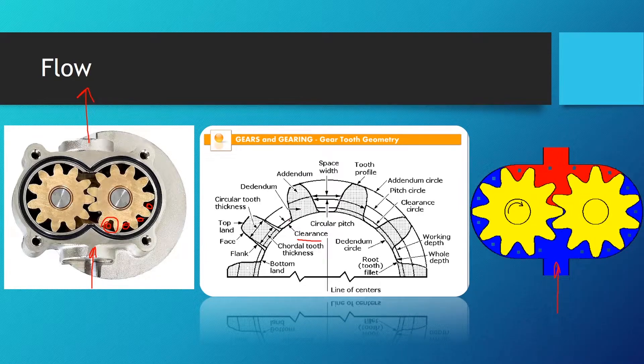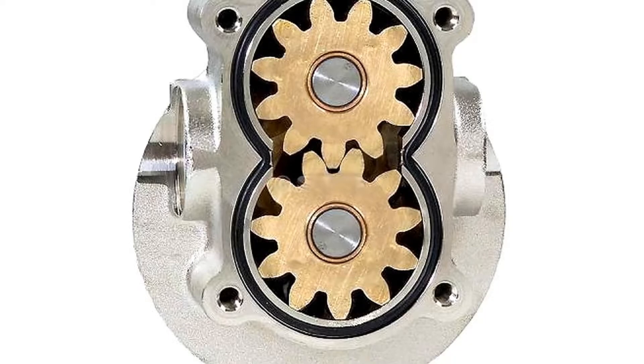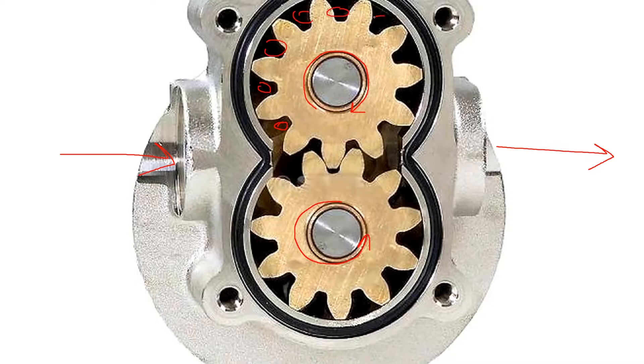Now remember this little clearance here. If we look at this gear pump up close, this is our inlet port and this is our outlet port — this gear goes clockwise and the other counter-clockwise. Fluid gets trapped and pushed to the outlet side. This area where the fluid is trapped is actually a volume, because we also have the width of the gear b. We multiply this area by the width of the gear to get the volume of working fluid going through the pump.